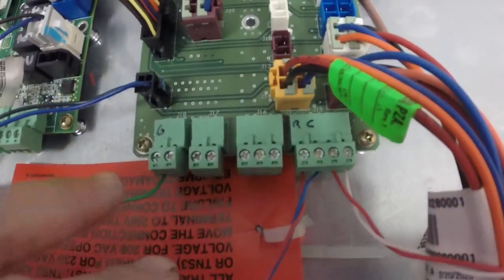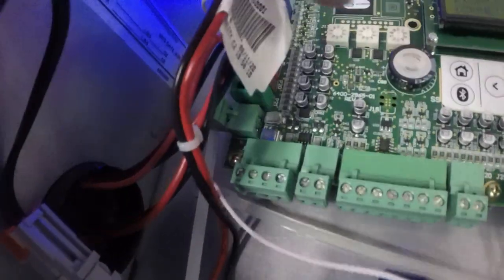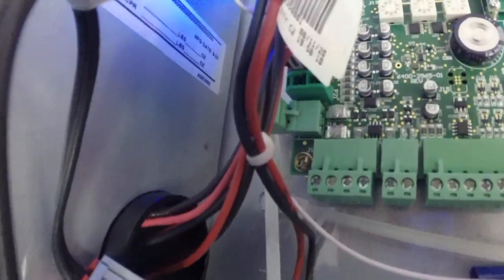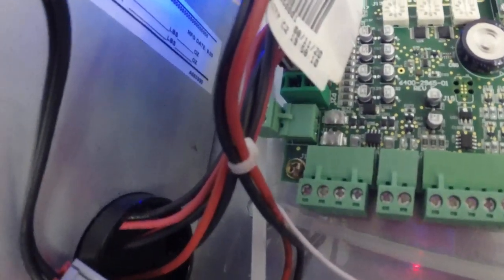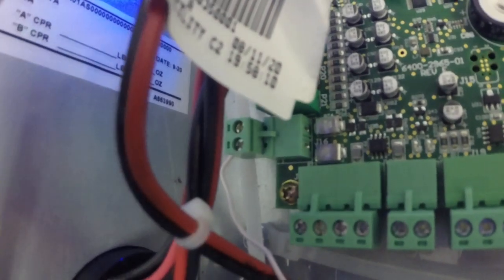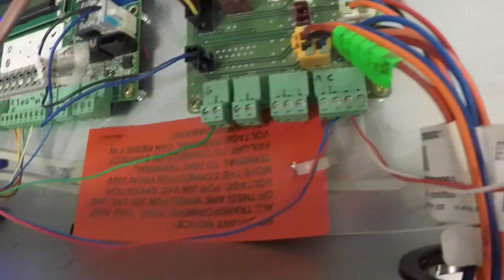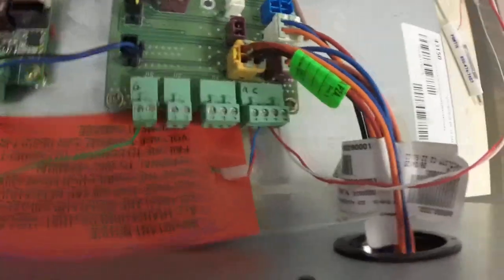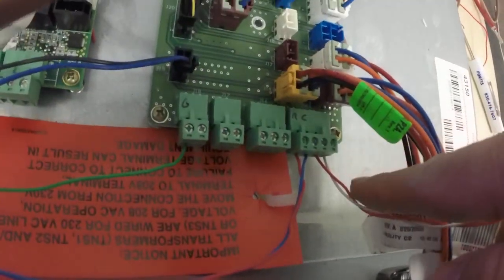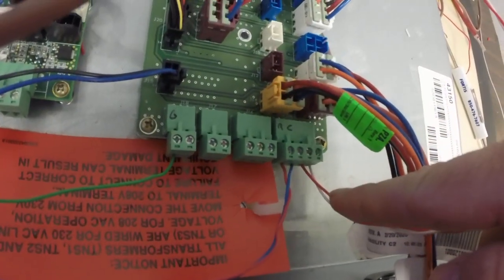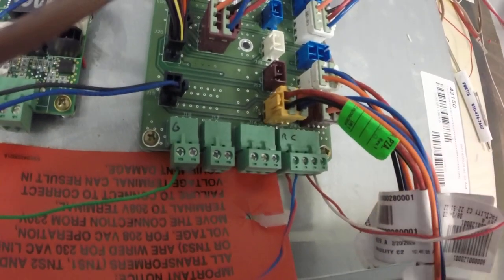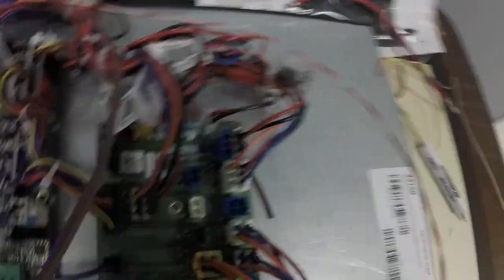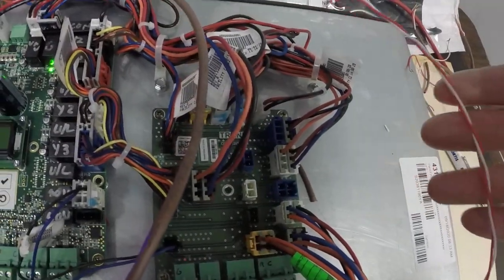So five conductors here and then if you follow this over here to the Symbio 700 board, that pin right there is going to connect your evaporator defrost. So we've got that connected so a total of six conductors all together. Remember for your IMC communication you do need to have twisted shielded pair. So I've kind of rigged up something here with my twisted thermostat wire.